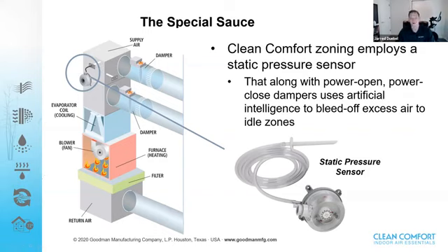We'll talk about that a little bit further here in a bit, but like Jonathan had mentioned with the barometric or electronic bypass dampers, typically you'd have that installed in that section of ductwork. So you'd either set it by means of a weighted arm, or you'd set a static pressure sensor there on electronic type bypass, and you'd have to set it so that when you reach a specific level of static pressure or resistance in the system, it would open up that damper and we'd start automatically bleeding air that we have already conditioned straight from the supply right back into the return.